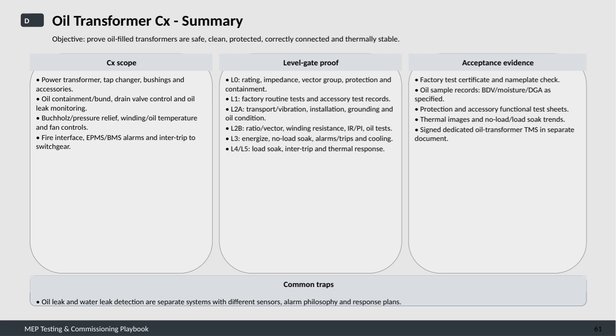It includes factory test certificates and nameplate verification, detailed oil sample records assessing breakdown voltage, moisture content, and dissolved gas analysis as specified. Functional test sheets for protection and accessories are reviewed alongside thermal images and soak test trends under no-load and load conditions. All this data is compiled in a dedicated oil transformer test and maintenance schedule maintained as a separate document. One common pitfall to watch out for is confusing oil leak detection with water leak detection.